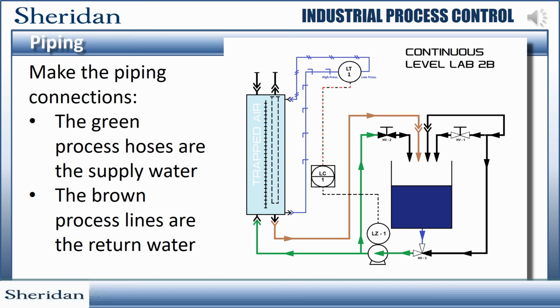On the calibration video, an additional hand valve and small feeder hose is added to the supply piping. This allows the technician to close the valve and trap the water at a particular level while doing the calibration. This P&I drawing shows the final drawing used in the continuous measurement lab, whereby the additional hose and valve are not used.